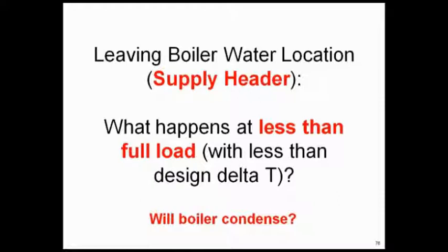So humor me for just a second. A real simple question here. Let's put it on the system supply side and see what happens at less than full load with the delta T and return temperatures, and ask the question, will the boiler condense? That's kind of the question we've got to have.